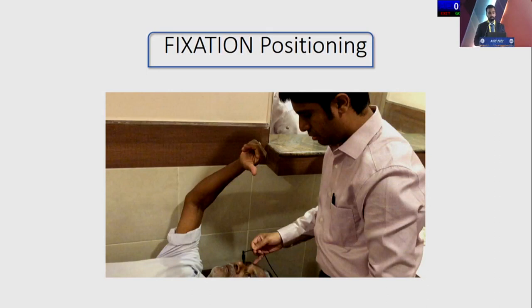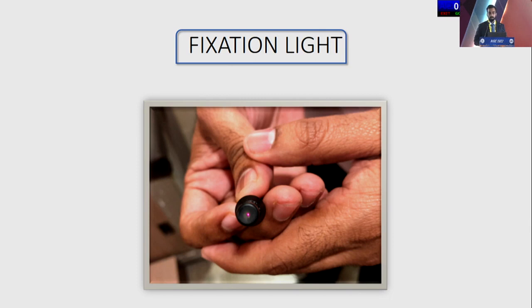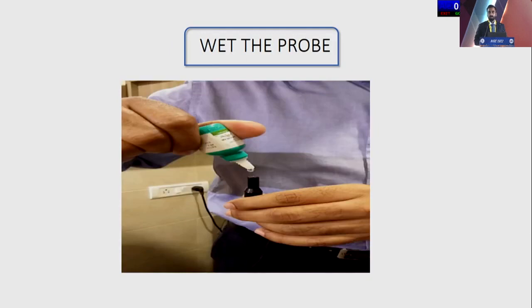So here is an example of a good A-scan measurement where the patient's head is parallel to the floor and the iris is parallel, and the patient is looking up at his own thumb to fixate, and the probe is being held by the wire to avoid the chance of any corneal compression effect. So this is the fixation light that the patient can be asked to look at to enhance the patient cooperation. It is also ideal to wet the probe before going ahead with any A-scan measurement, because measuring on a dry cornea can also give rise to a fallacy in the results.